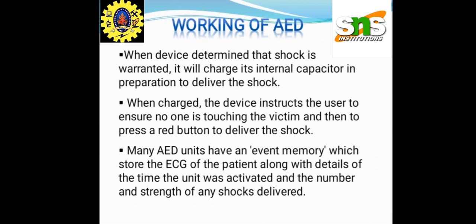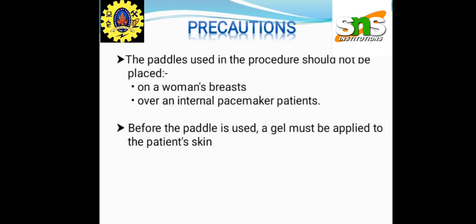Many AED units have an event memory which stores the ECG of the patient along with details of the time the unit was activated and the number and strength of any shock delivered. Precautions. The paddles used in the procedure should not be placed on a woman's breast or on an internal pacemaker patient's.